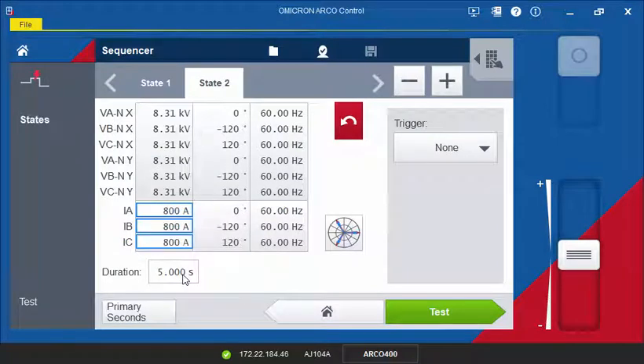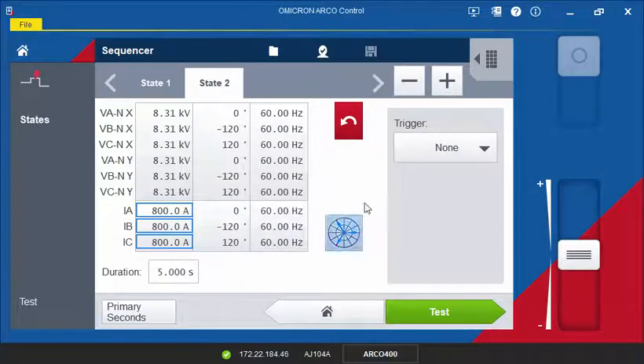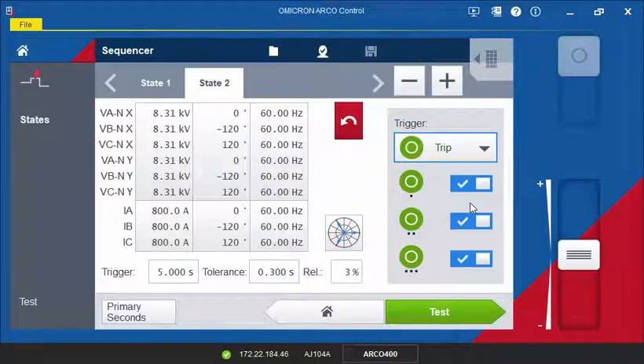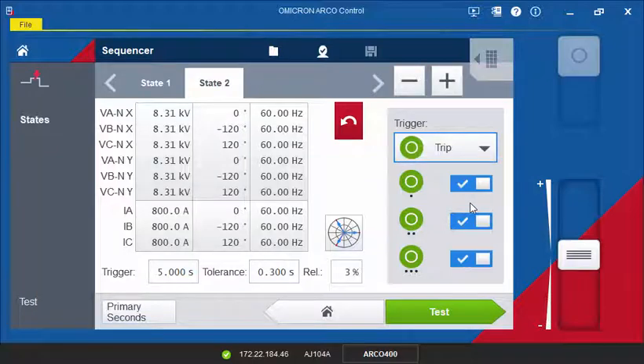For this current, we expect the recloser to trip. We define a trigger on the trip signal. As soon as the trip signal is detected, the state will end and the sequence will move on to the next state.